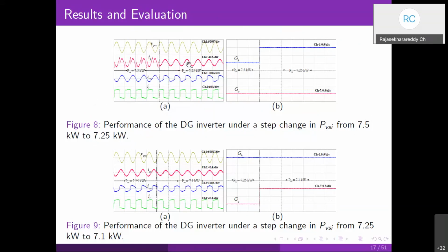So you can see the variation in the grid current waveform and the inverter current waveform, and also the variation of these compensation factors. As long as the inverter is fully loaded, the grid current is seen to be distorted because it is supplying load harmonics as well. Once the DG power generation is reduced, the remaining capacity is being used in compensation of the active, harmonic and reactive currents. So you can see the improvement in the grid current, and also the change in the wave shape of the voltage source inverter current.